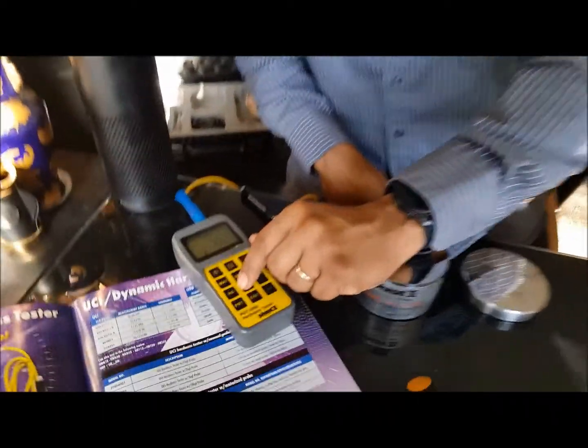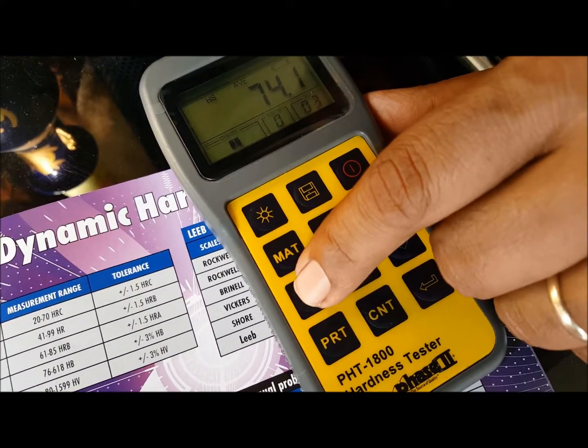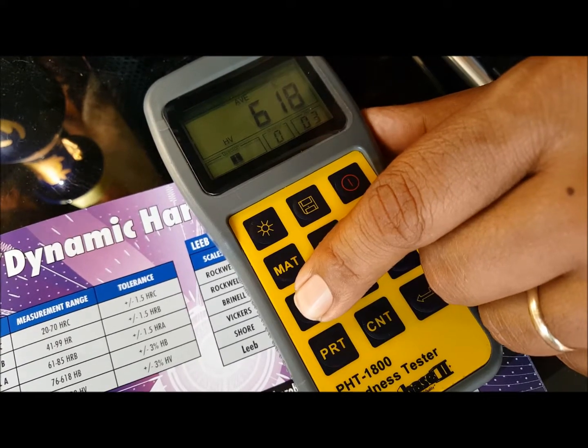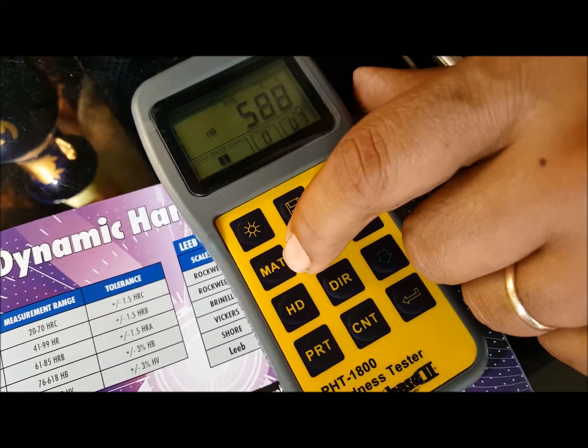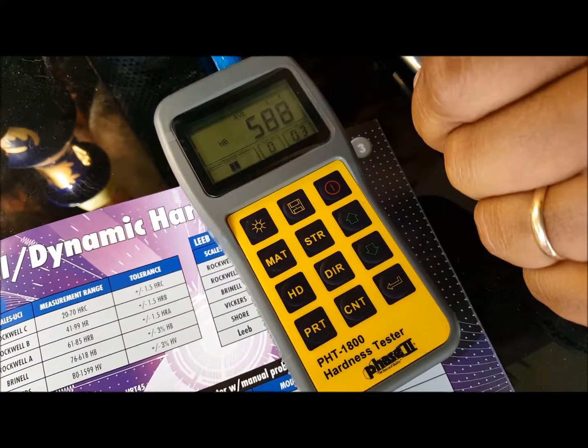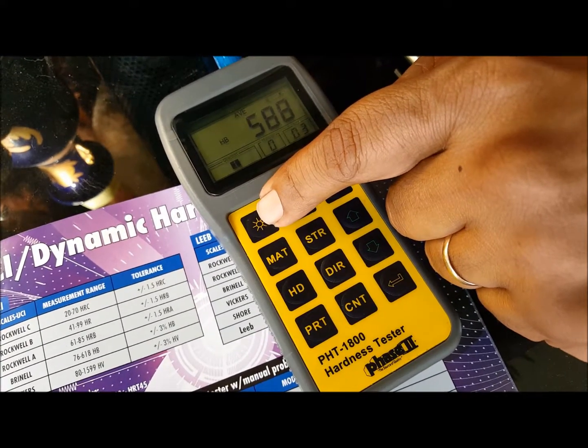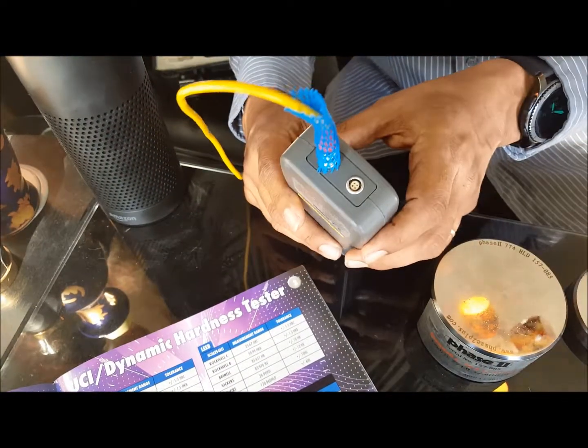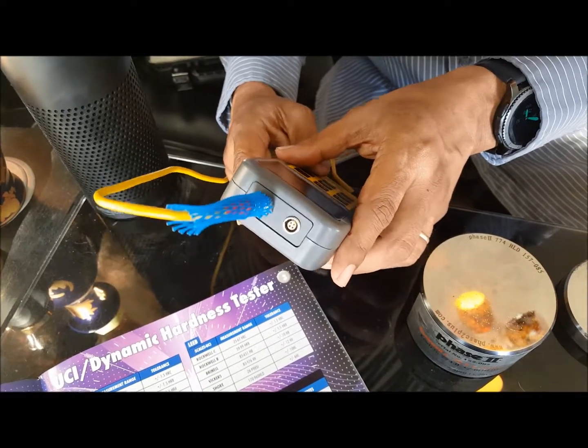What's cool about this — if you zoom in — you've got here, you can go from the different scales: Shore, Rockwell B, LEEB, Vickers, Brinell, and you can go between different materials too, depending on what you're using. There's a Save button where you can save your results, a power button in case you need a backlight, and over here it does come with a cable where you can connect it to the computer, so you can print out some basic printouts.